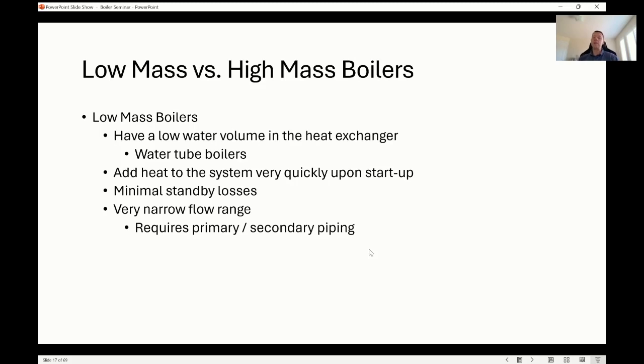So let's talk about high mass and low mass stainless steel condensing boilers. When I'm talking about mass, I'm talking about water mass. Basically, a low mass boiler has less water in it. A high mass boiler has more water in it. So a low mass boiler is basically a boiler that has minimal water mass in it. They generally tend to be water tube type appliances where the water's flowing through the tubes and it's surrounded by the flue products. Now, these type of appliances tend to have very specific flow requirements. I find, they might allow you to vary it a bit depending on the manufacturer and the type of heat exchanger. But for the most part, I find these type of appliances like static flow, and they generally have a very narrow range between the minimum and maximum flow through it. Some manufacturers just have a static flow that they want: give me this and nothing but. And as a result of that, when I'm dealing with low mass appliances, I always recommend primary, secondary piping for them.